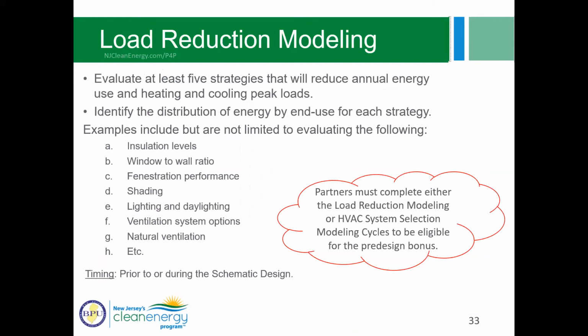Then there's load reduction modeling. Here we want to evaluate at least 5 strategies that will reduce annual energy use and heating and cooling peak loads. And you want to identify the distribution of energy by each end use for each strategy. Examples include, but are not limited to, evaluating insulation levels, window to wall ratio, shading, and natural ventilation strategies. There are many different options. This needs to be completed prior to or during the schematic design phase. And as I said before, partners must complete either this and the elements of the simple box and conceptual design modeling that I just discussed, or the HVAC system selection modeling in order to be eligible for the pre-design bonus.